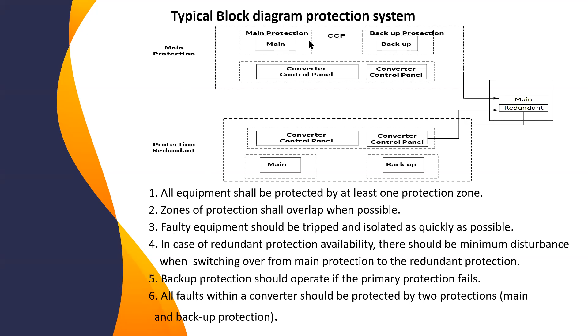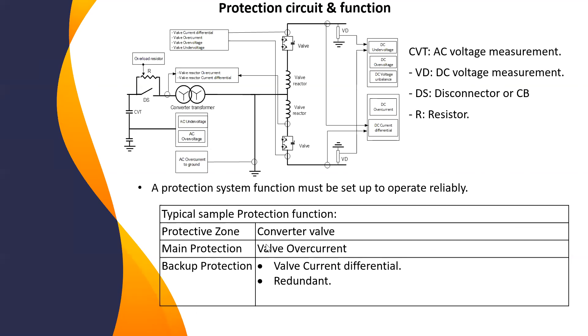So this is typical, not really reflecting any particular design. When we are talking about converter valve protection, this is one example I take here. Let's say we have main protection, valve overcurrent, and then we have backup protection, differential, and then we have redundant protection as we mentioned. So this is an example of how protection works in an HVDC scheme. And then the next one, how we see a fault on DC transmission line. In DC transmission line, actually always a circuit breaker isolates the fault here.